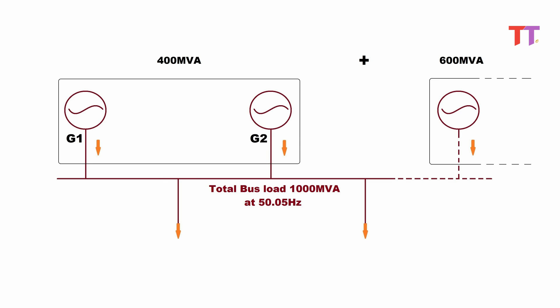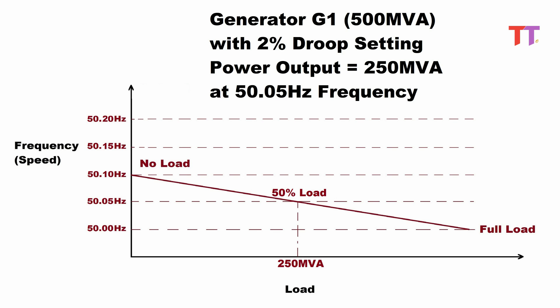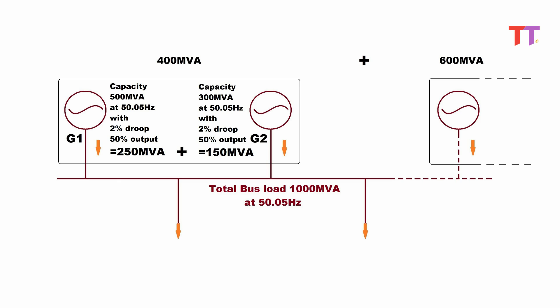Generator G1 and Generator G2. Generator G1, with a max load capacity of 500 MVA, is loaded at 50% using a 2% droop setting. Reference speed is set at 50.10 Hz. Hence G1 is 50% loaded, delivering 250 MVA load at 50.05 Hz speed, which is bus frequency. Similarly, by setting reference speed at 50.10 Hz, Generator G2 with 300 MVA capacity is loaded at 50%, delivering 150 MVA load at 50.05 Hz speed. This is how G1 and G2 deliver 400 MVA power to the bus.